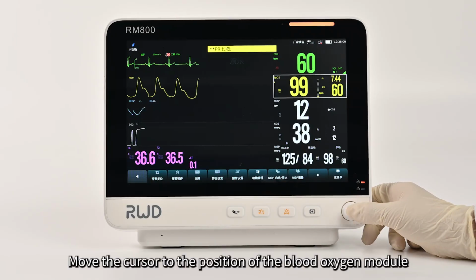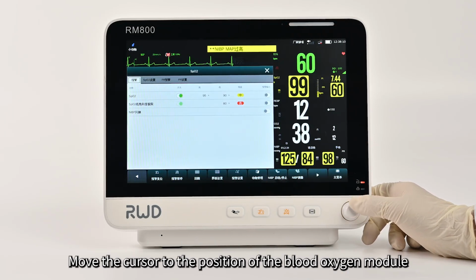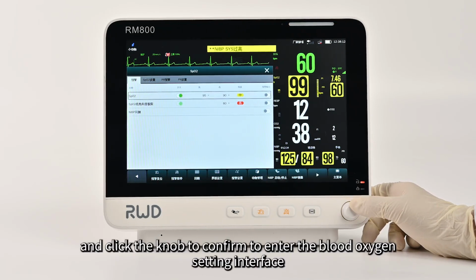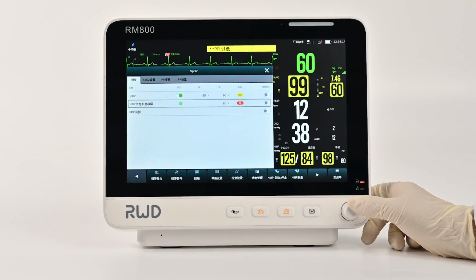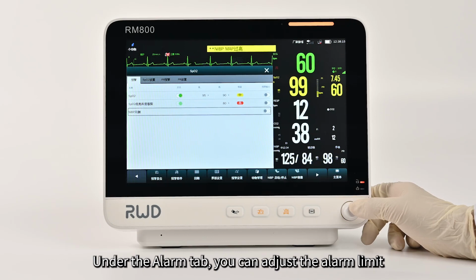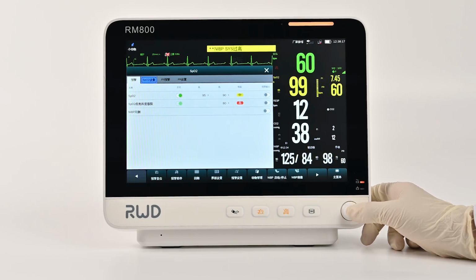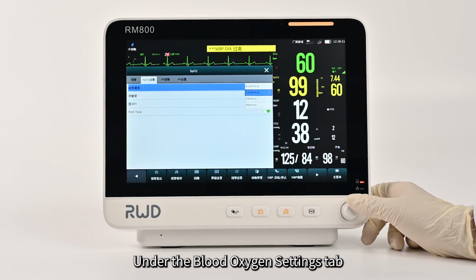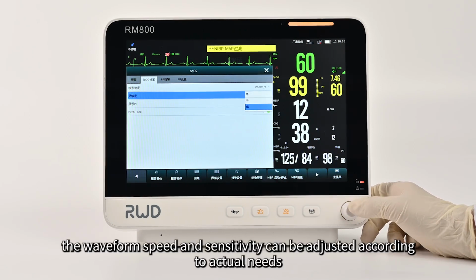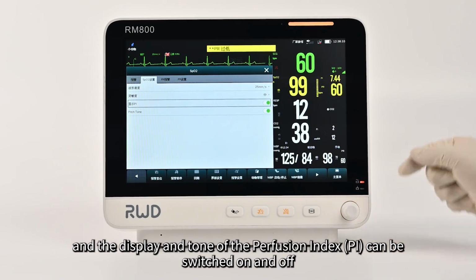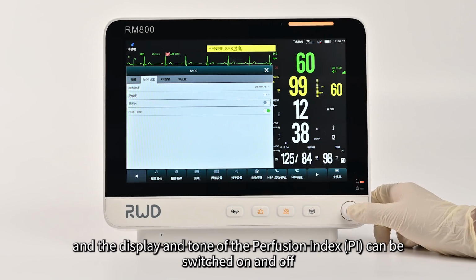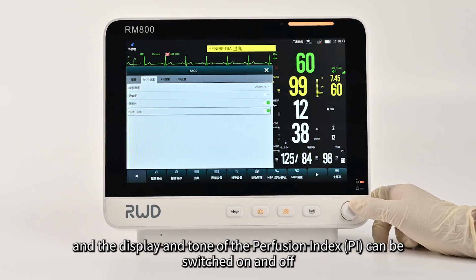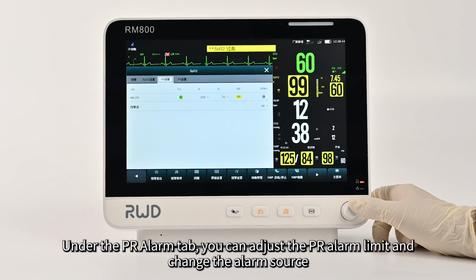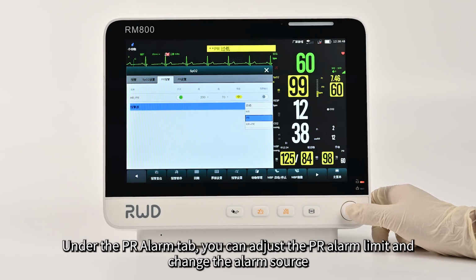Move the cursor to the position of the blood oxygen module and click the knob to confirm to enter the blood oxygen setting interface. Under the Alarm tab, you can adjust the alarm limit. Under the Blood Oxygen Settings tab, the waveform speed and sensitivity can be adjusted according to actual needs, and the display and tone of the perfusion index (PI) can be switched on and off. Under the PR Alarm tab, you can adjust the PR alarm limit and change the alarm source.